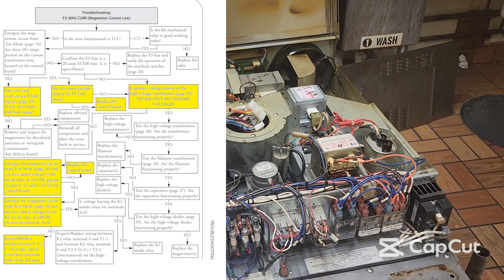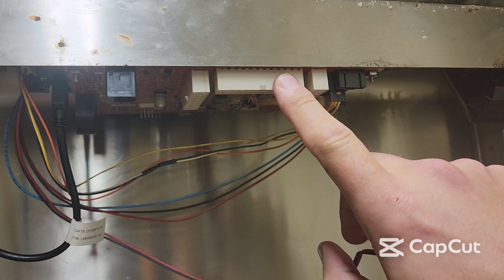So there's some rules on that one. If you're drawing more than 10 amps, but it's still giving an F3 mag current error, according to the document we have, you should look at your control board, this guy right here. Your control board is going to basically control your ins and your outs, and if it's not seeing 10 plus amps, it will give an F3 mag current error.